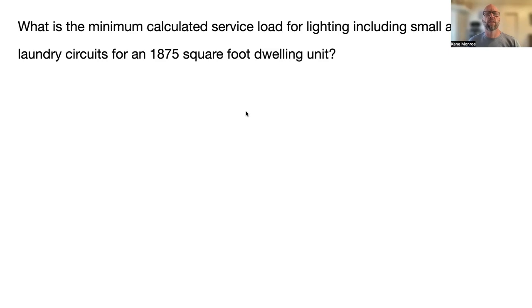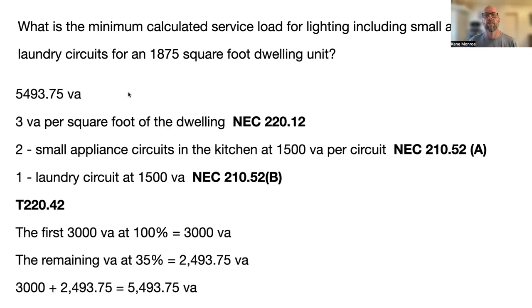Next question: what is the minimum calculated service load for lighting including small appliance and laundry circuits for an 1875 square foot dwelling unit? The answer is 5493.75 VA. Go to NEC 220.12 — for a single or multi-family dwelling, you calculate 3 VA per square foot. So we take 1875 and multiply by 3, and set that number aside.